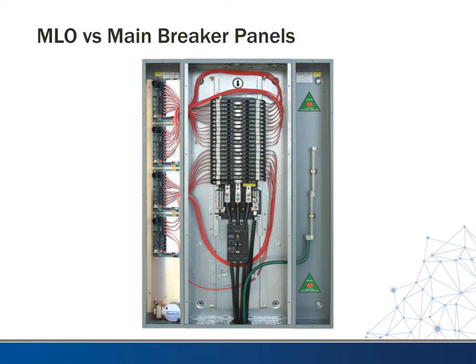So here is an example of a panel that has a main breaker. So you see the feeder coming in here and it goes through this larger breaker first. And so this is your main breaker, and then it goes from this breaker to these lugs. So if the breaker wasn't here and the feeders came in and just landed straight on these lugs, these would be main lugs. So this would be your main lug only panel.